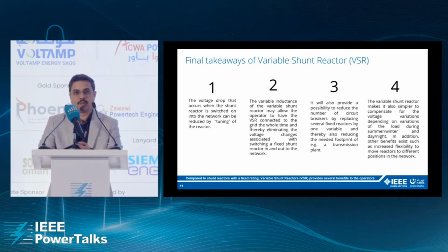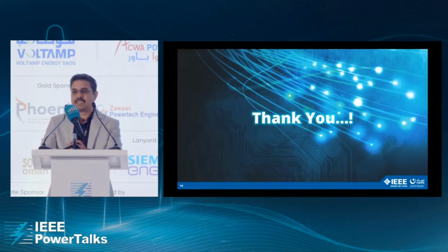And last but not the least, the variable shunt reactor not just compensates the reactive power, but it's also flexible to absorb or maintain voltages when there is a demand from different weathers. Like in most countries, the demand for power varies from summer to winter. So even in those conditions, a VSR can maintain the voltage level. And most important is this flexibility in nature, like it can adjust itself to the output demand. We can place a variable shunt reactor at different nodes or different positions within a power system, making it more and more flexible from the investment point of view or from the installation point of view. So that's all from my side. Thank you for listening.